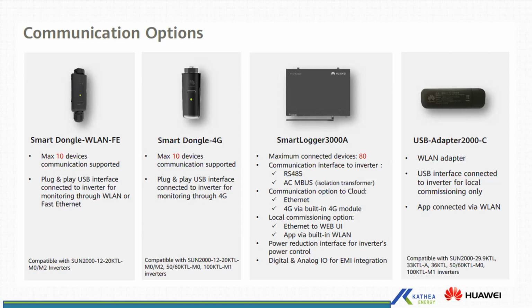So the inverter also has a power reduction interface for inverter power control. That is the ripple control interface. And then it has digital inputs and analog and digital inputs for weather station integration. That is the EMI. These digital inputs can also be configured to control external devices, or to actually switch off inverters through external devices, like emergency stops and all that.